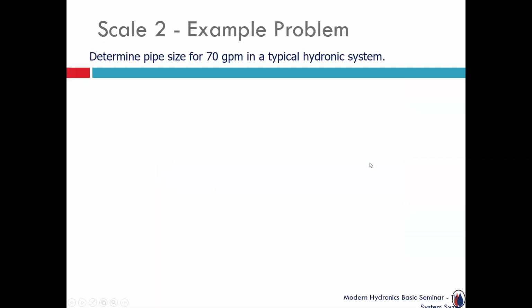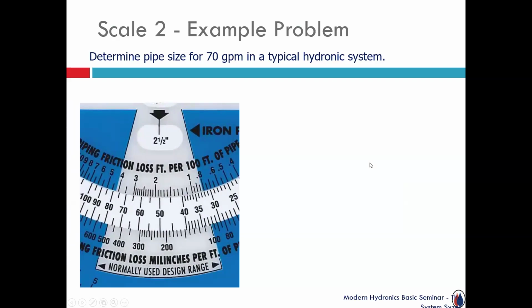So another quick example. What size pipe do I need for 70 gallons a minute in a typical hydronic system? As you take the wheel on scale 2 and you're scrolling through, you're saying, hey, where's 70 GPM? And typically speaking, the desire is to not spend too much money. So I don't need to necessarily oversize the piping, because I'm going to be buying more expensive pipe and more expensive fittings. And then I don't want to go on the other side and undersize the pipe and create some real excessive pressure drop and/or velocity. So I'm trying to find that mid-range.